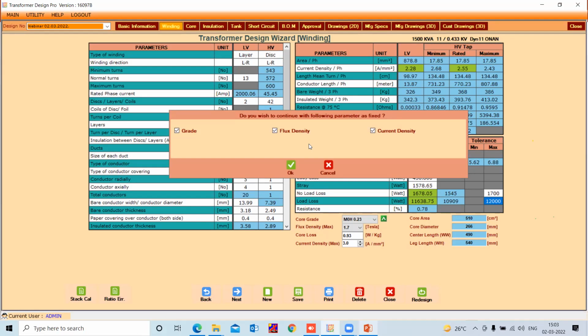We have changed the grade, we have changed the flux density, we have changed the current density. And with the change parameters, currently we have changed and come back to it. But however, if you have changed and remained at that level, this kind of question will prompt you to decide that with the change parameters, whether you wish to design the transformer again. Again, another 1 minute it will take, and it will fix these values and make sure the transformer design is completed. Let us see friends, now after this, I'll take you to the core grade.